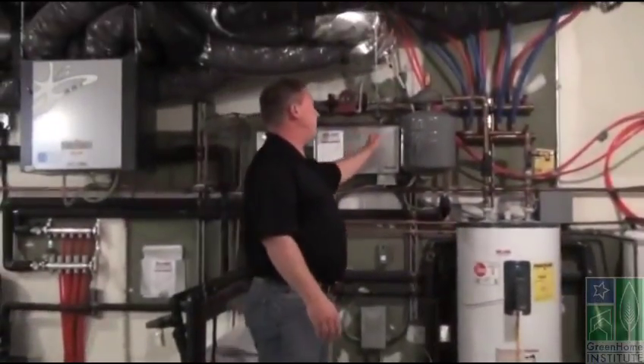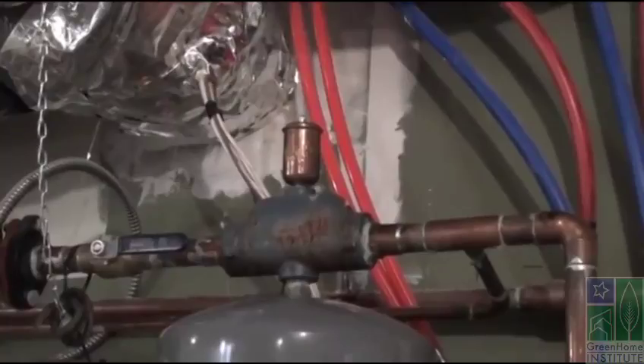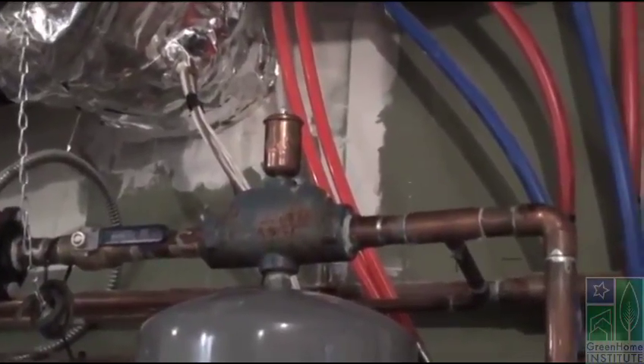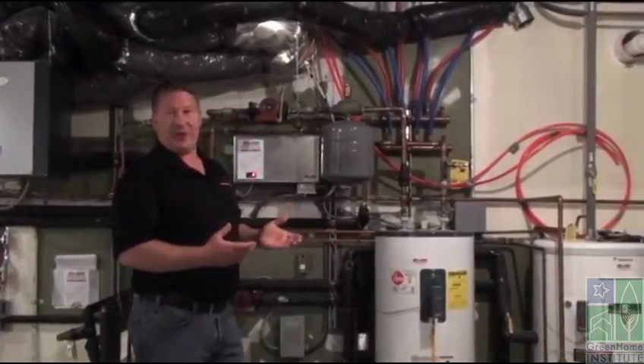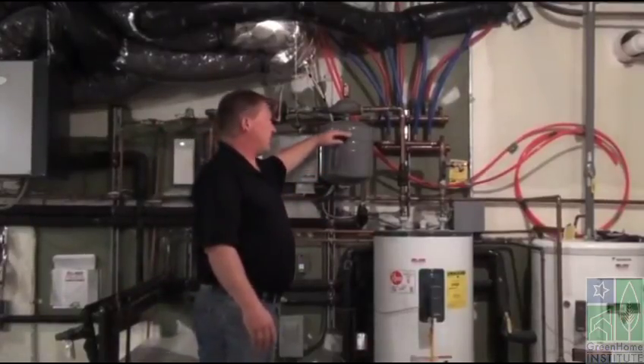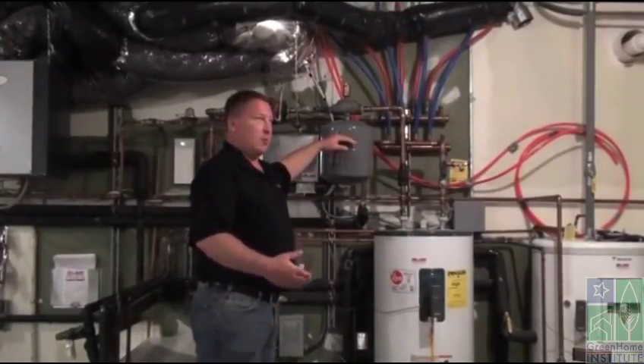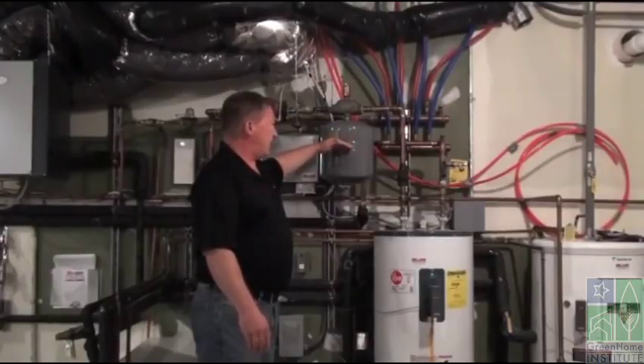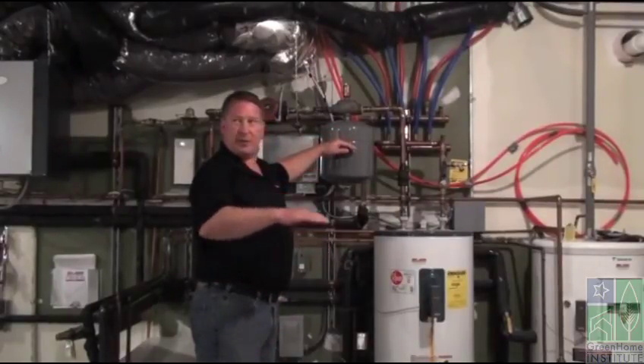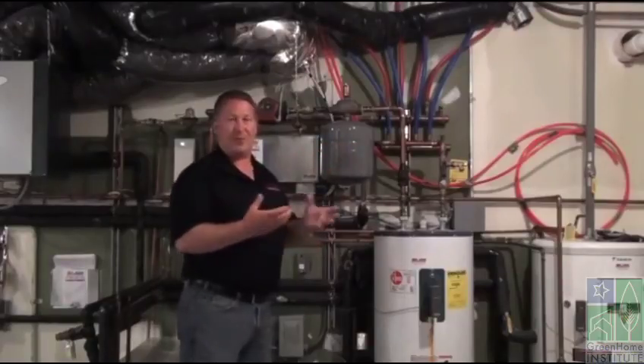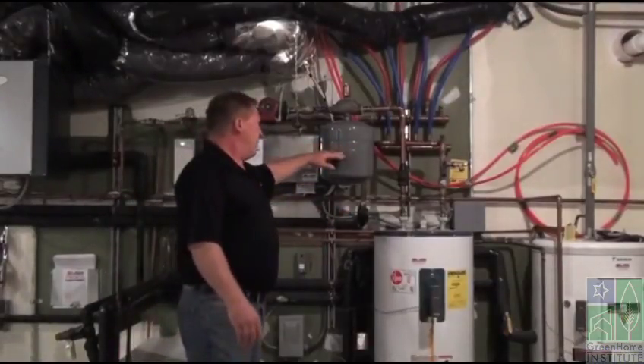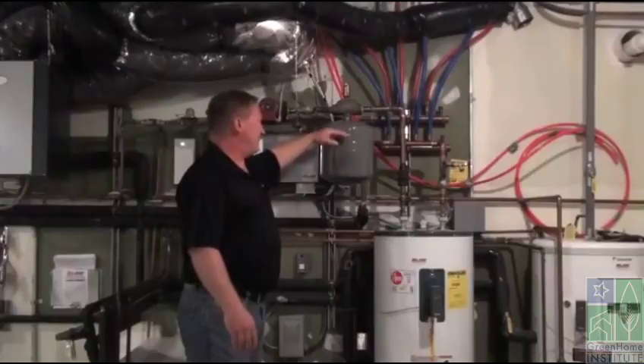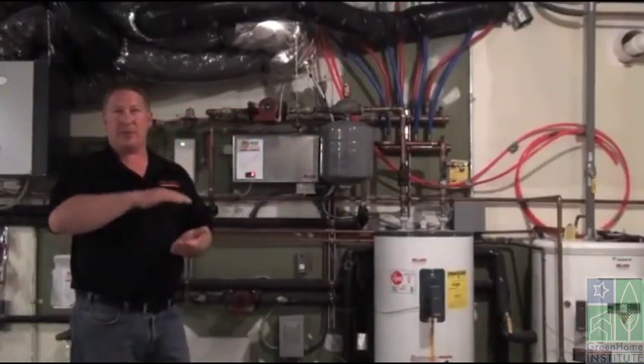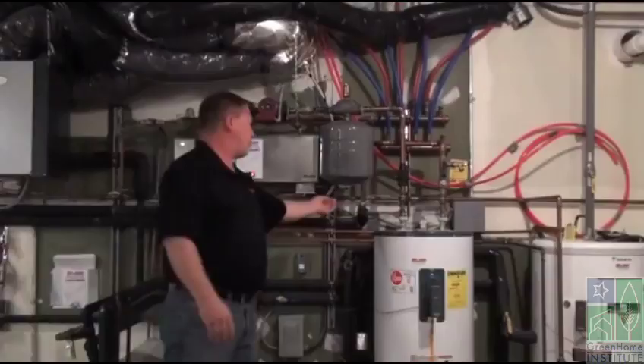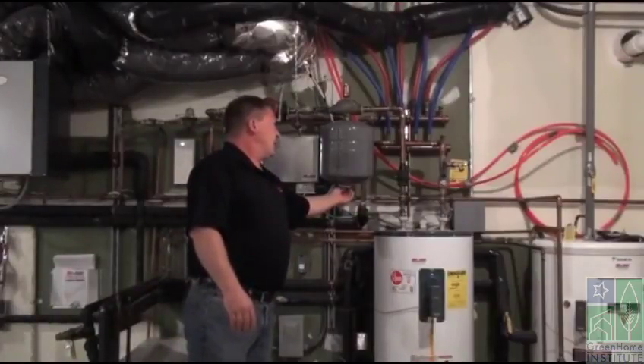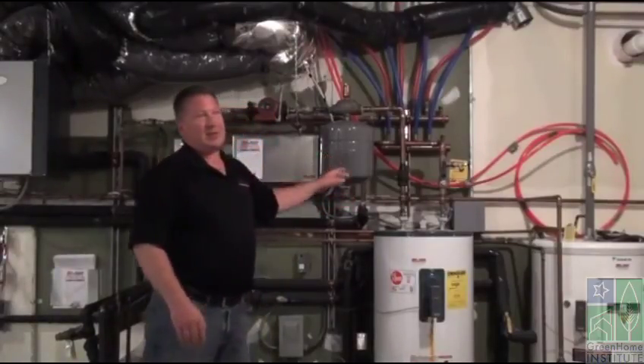There's also an expansion tank on this system with an air separator. As water heats up, it expands and takes up more volume, and the pipes aren't going to expand, so there's a bladder tank here that allows for that expansion. And again, when the water warms up, it expands, and there's a bladder in there, kind of like a balloon, that allows the extra water from the expansion to go into this tank. It doesn't actually hold water, a very little bit of water, but it's just a bladder that depresses. This is under pressure. Really doesn't need to be checked unless, again, there's a problem.